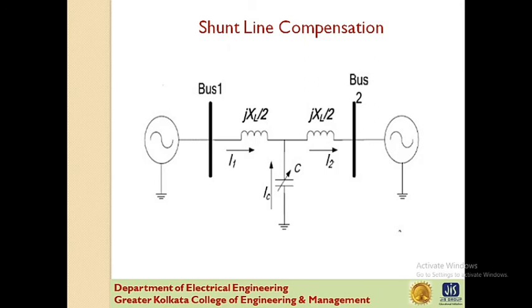Similarly, in systems with large capacitive effect, shunt reactors must be connected under light load conditions to avoid overvoltages. This is often the case in extra high voltage systems where power transfer over long distances, limited by stability considerations, is below surge impedance loading. Now this requires shunt reactors to absorb the excess reactive power generated, to avoid the Ferranti effect.